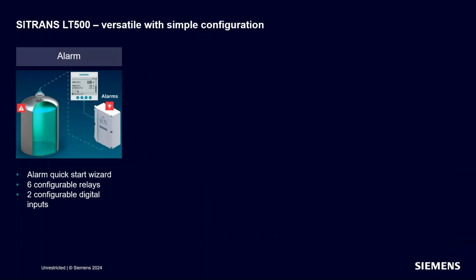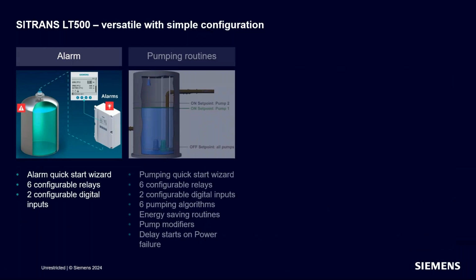Using the Quick Start wizard, you can set up all of your alarms, now up to 6 alarms. That's something we ask prior to ordering, because those alarm relays are actually installed in the box. So we ask if you want 1, 3, or 6 relays, those are the available options. Once you get the unit, depending on those relays, you can configure them using the Quick Start wizard to utilize them in any shape or fashion you would like.